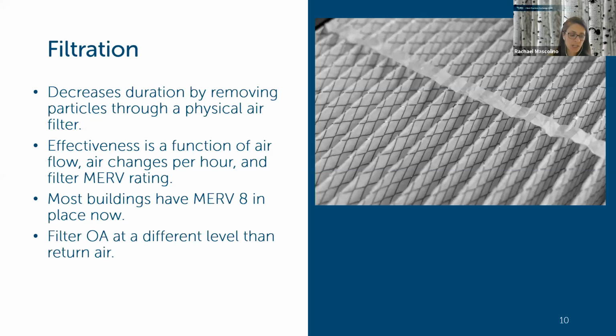So the next priority is air changes and filtration. And I think about these together because the number of times that the air is passing over the filter in an hour is going to impact the effectiveness of that filter to clean the air. The recommendations from ASHRAE and the CDC and Harvard is to increase the return air filters to MERV 13 when possible. And I want to highlight that last bullet there: filter the outdoor air at a different level than the return air.